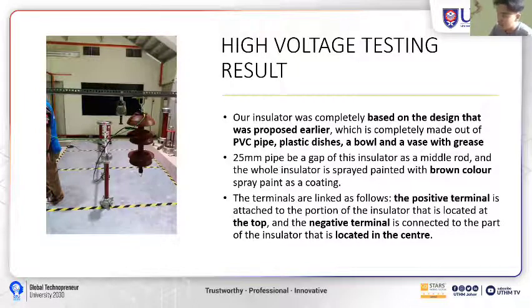Based on the insulator prototype, we have made the testing, which is the high voltage testing at Batu Pahat. The insulator was completely based on the design that was proposed in the proposal, which is made up of a few materials such as PVC pipe, plastic dishes, bowl, vase, grease, and cement. The pipe, which acts as the rod of the insulator, is filled with the grease and cement, and all of the assembled prototype was sprayed with brown color coating.